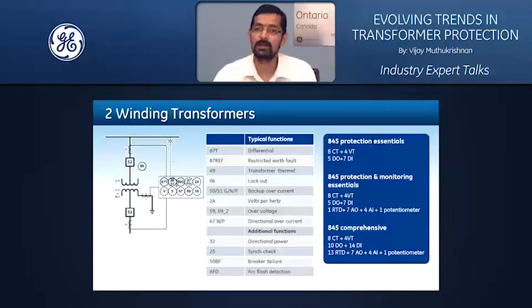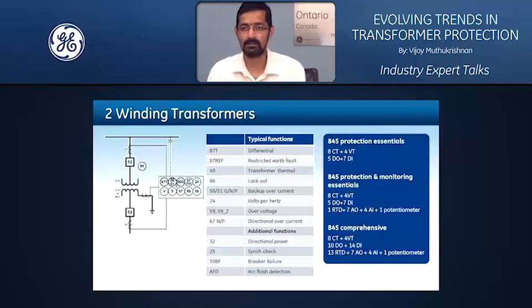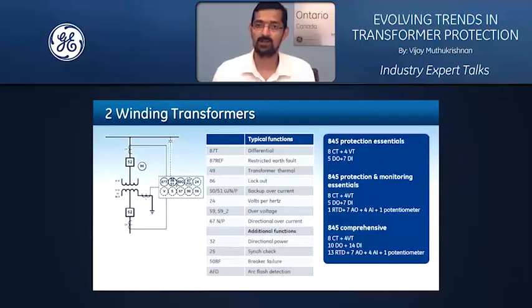In medium voltage applications, you are also going to benefit by having an integrated arc flash protection module that can detect arc flash. That's the scope of protection functionalities you can expect when you have a two-winding transformer protection application with voltage input coming in. In our 845 transformer protection relay, you can achieve this easily by having an 8CT current analog subsystem and adding on a 4VT voltage subsystem combined with a combo IO box. That can give you the base level of protection.